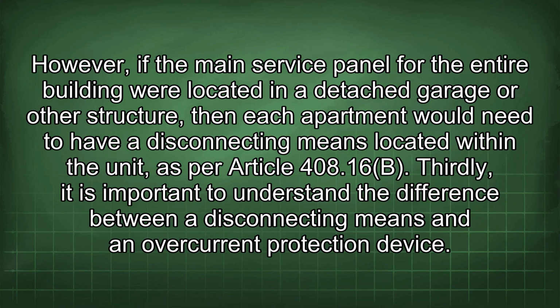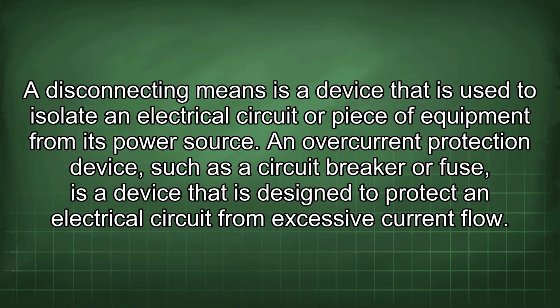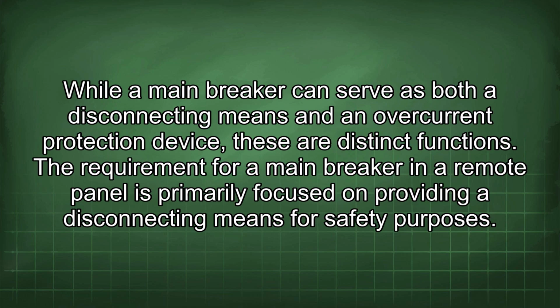Thirdly, it is important to understand the difference between a disconnecting means and an overcurrent protection device. A disconnecting means is a device that is used to isolate an electrical circuit or piece of equipment from its power source. An overcurrent protection device, such as a circuit breaker or fuse, is a device that is designed to protect an electrical circuit from excessive current flow. While a main breaker can serve as both a disconnecting means and an overcurrent protection device, these are distinct functions.